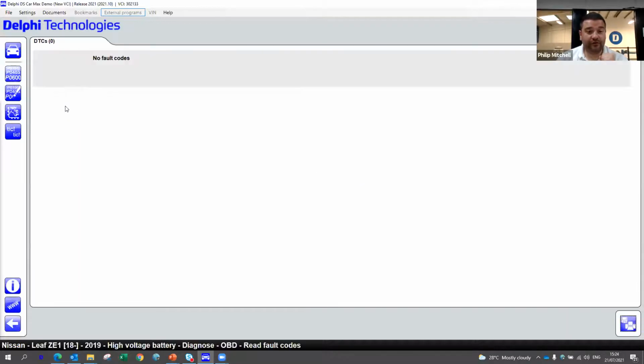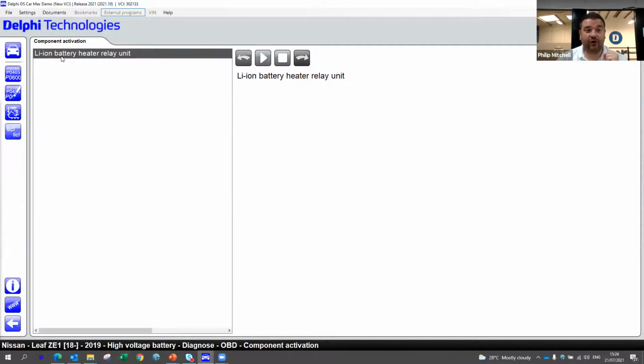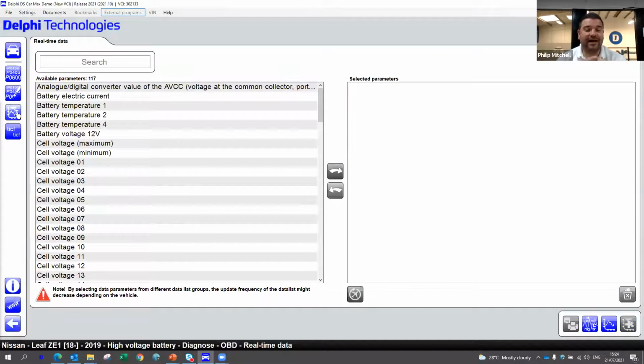So let's quickly look at the fault codes - no, there's nothing there. And on the activation side, we've only got the option for the relay heater unit. So what you'll see is that we don't have any function to run an automated health check.